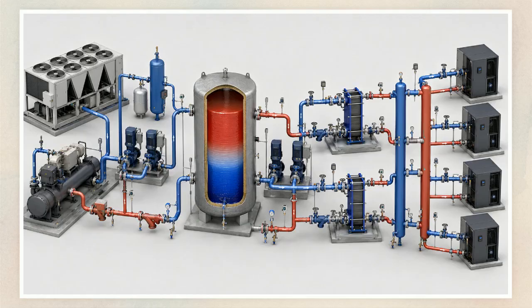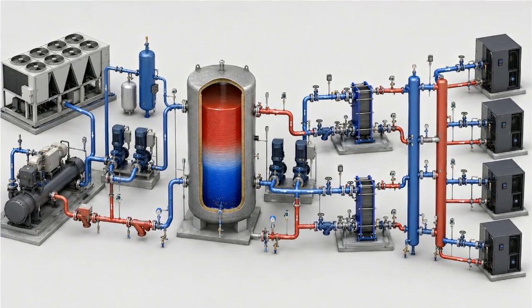This diagram shows the spatial relationship across that boundary. On the exterior, you have the primary production side, the air-cooled chillers. Inside the boundary, you find the critical delivery side, which includes the central stratified tank and the data hall CRAH units. Sizing this protection requires exact baseline inputs.